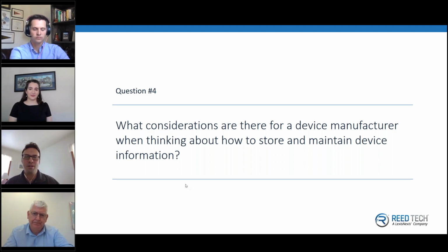Even if you're in a situation where you have a handful of devices and it is rather static, let's say, very mature products, you're submitting UDI electronically, creating electronic records and submitting those to regulatory authorities. So it's probably a good idea that that's maintained in a controlled fashion. All the initial submissions had an audit trail applied with them. I'm sure if there are any quality colleagues on the line, the expectations are probably pretty high for maintaining that in a controlled fashion.